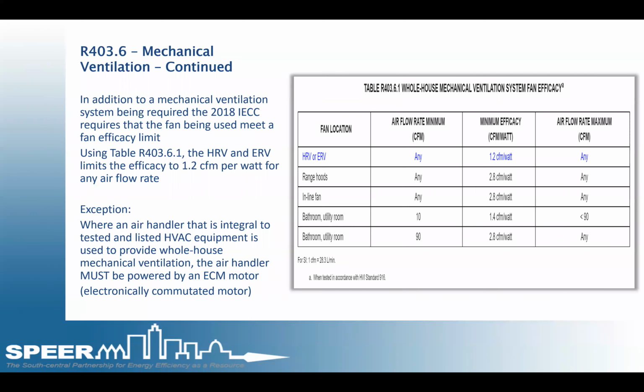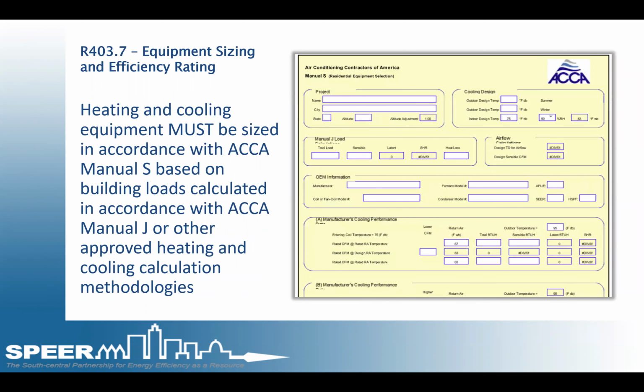With this exception that's listed, any and all blower motors on the market today are ECM controlled, which means they can ramp up or down when the fan speed needs to be faster or slower. This does make them more energy efficient. However, a bit of caution again on this. Using the performance path, which most builders do, it is not easy to get an energy model to pass, even when using an ECM motor. In the 2021 code, it even makes it harder, and that did start with 2018. Less and less homes will pass energy modeling per the 2018 and 2021 and beyond by using the air handler. That is usually not something that you want to do.